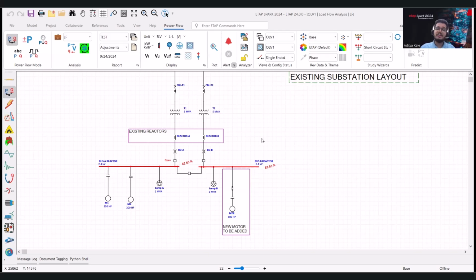So now, given our initial starting voltage of 82%, starting a large horsepower motor in this configuration is almost impossible. The reason we say that is during the motor acceleration, this voltage is going to further drop an additional 15 to 16%, which takes it close to the contactor's drop-off voltage. So during the starting of this motor, there is a chance that these contactors might just open up and we lose the loads for no reason. This led to a conclusion that we cannot start the motor with the reactors in place.